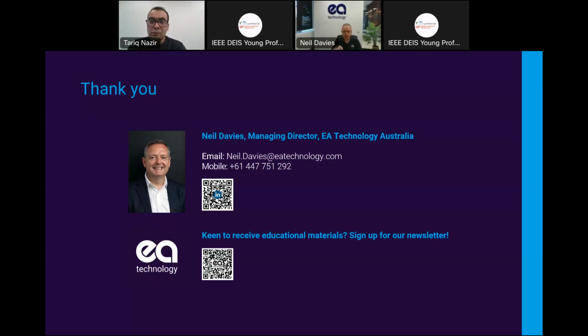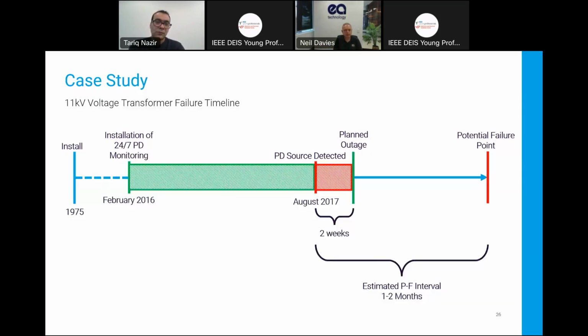What you don't actually know is which phase you're measuring. So if you're measuring on a piece of switchgear or a cable and you're measuring red, white, blue phases, you know that your PRPD plot will be locked to a 50 Hertz or 60 Hertz signal, but you won't necessarily know which phase. But what you're really interested in is the interpretation of the PRPD, how that looks.